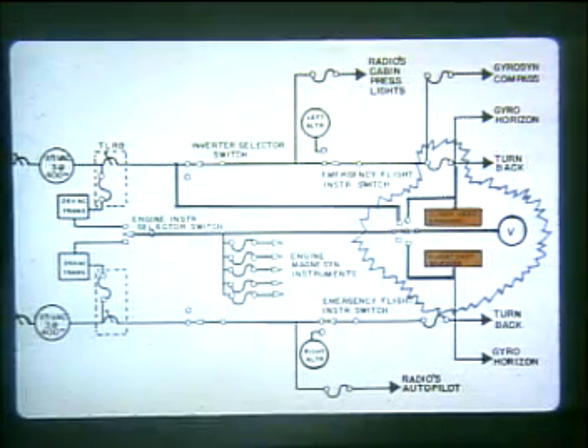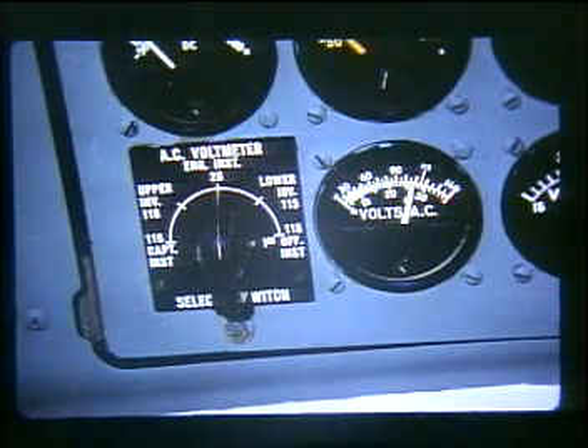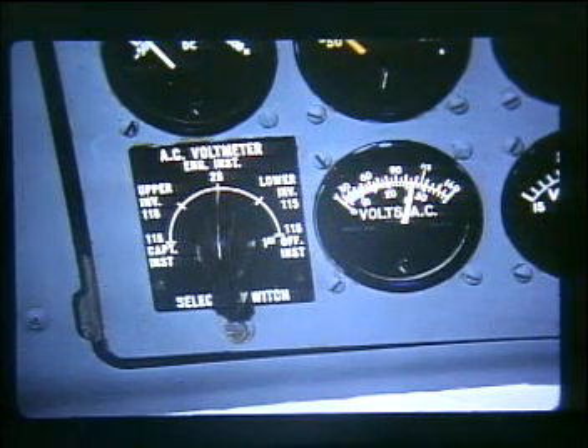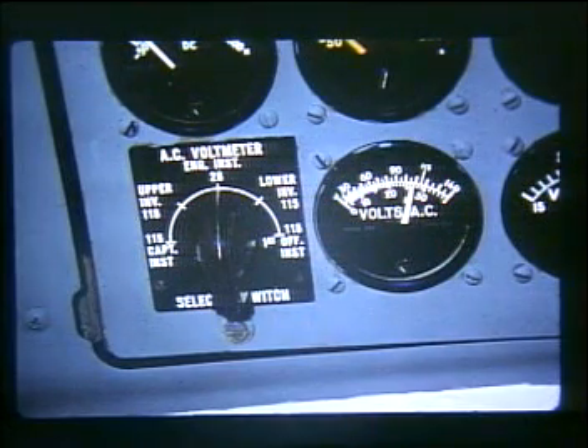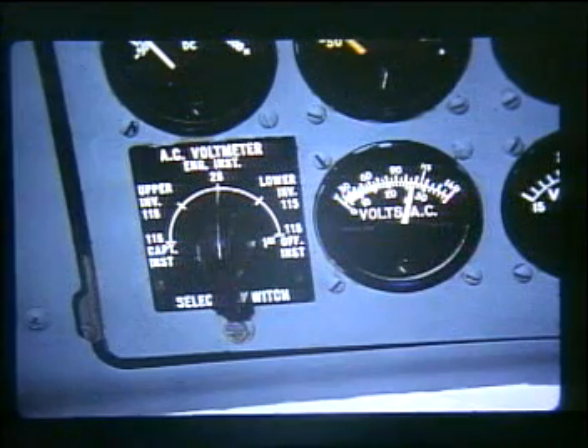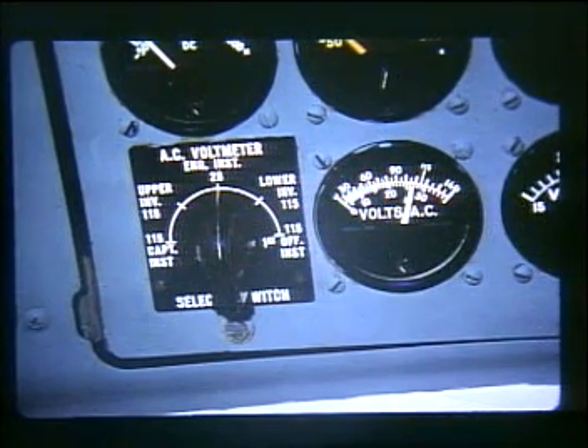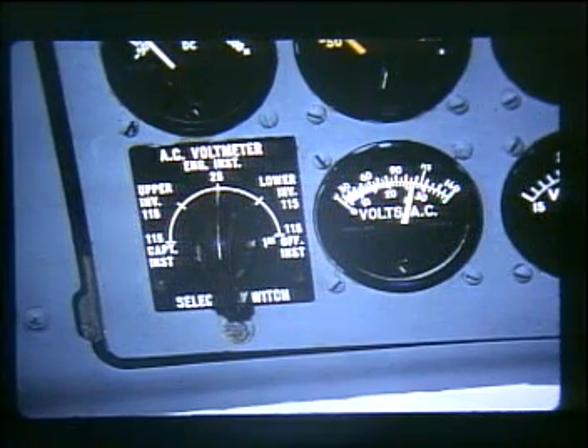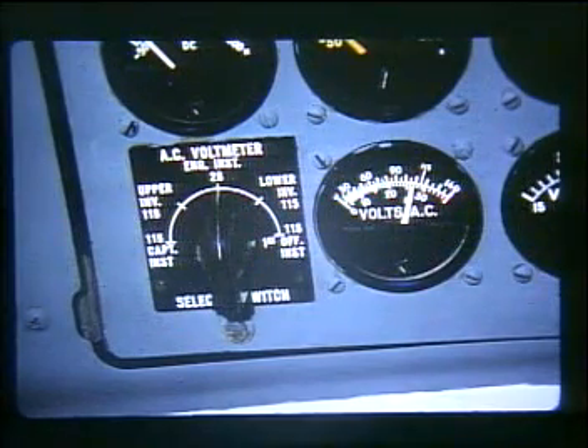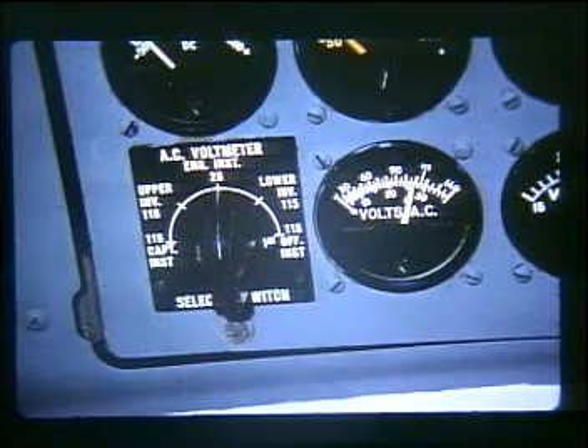The metering circuit in the Group 2 aircraft is basically the same as the Group 1, with the exception that the captain's and first officer's instrument voltage is now 115 volt AC instead of 26 volts AC. The only 26 volt AC used is for the engine instruments. The AC selector switch and associated AC meter are located on the generator panel in the same location as in the Group 1 aircraft. The voltmeter has been converted to a split-scale meter. Notice that the 115 volt indication is approximately opposite the 26 volt position, to the right of center. The selector switch has been changed slightly by placing the captain's and first officer's instrument position as the last positions of the switch, rather than adjacent to the engine instrument 26 volt AC position.